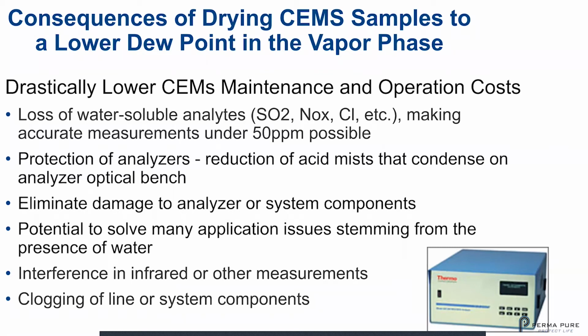They also protect analyzers. So we've reduced the amount of acid mist that condenses on the analyzer optical bench. This is very important. I'll show you in another slide how we eliminate over 80% of the water left behind by a cooler. And this makes it a lot less possible for acids to form ahead of the cooler. So we eliminate the potential for damage to the analyzer or system components. We have the potential to solve many application issues stemming from the presence of water. We also have reduced interference in infrared or other measurements because a lot of times the water interferes with the peaks given by the other components in those measurements. And we also reduce or eliminate clogging of line or system components.